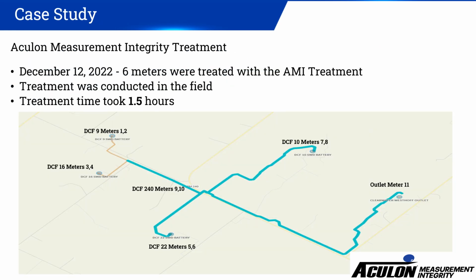As we searched for a solution to our continual meter cleaning, we came across Aculon Measurement Integrity in correlation with Kottmann. On December 12th of 22, we treated 6 meters with the AMI treatment. The odd numbered meters were our test group, and the even numbered meters were our control group. As we only had one outlet meter, we decided to go ahead and treat it to get the best results possible out of this closed loop system treating.